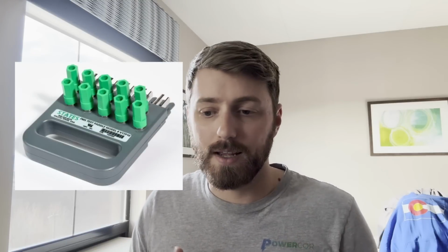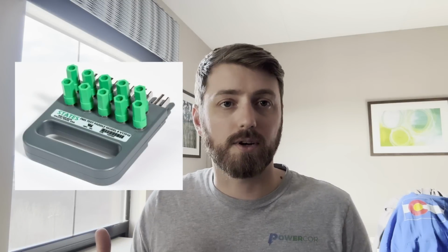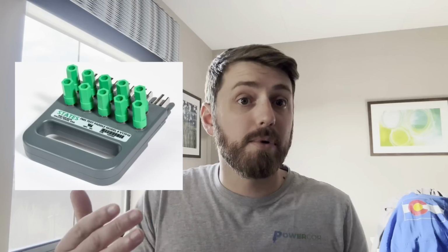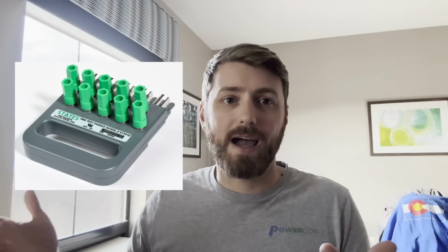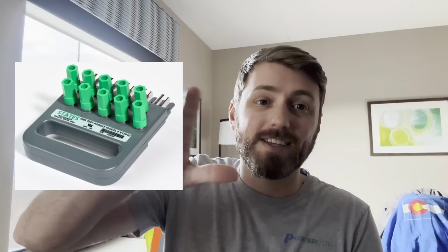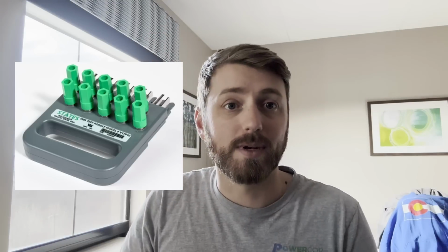All of them are designed so that a test switch paddle can be inserted and connect the relay test set or the current source on the top. That's just the only way that the paddle works, because it's physically connected directly to the relay itself.